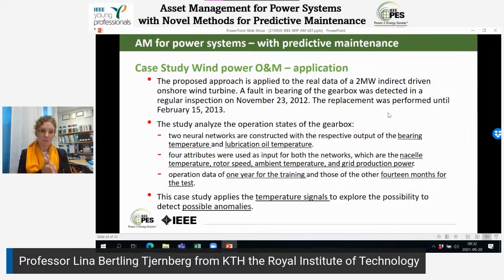In order to validate the model, we were very happy to get data where we had an actual fault happening and then a replacement. This gave us a way to validate and see if it was really possible to predict the fault before it happened. So in the model, we are using two neural networks, created with the output of the bearing temperature and the lubrication oil temperature.